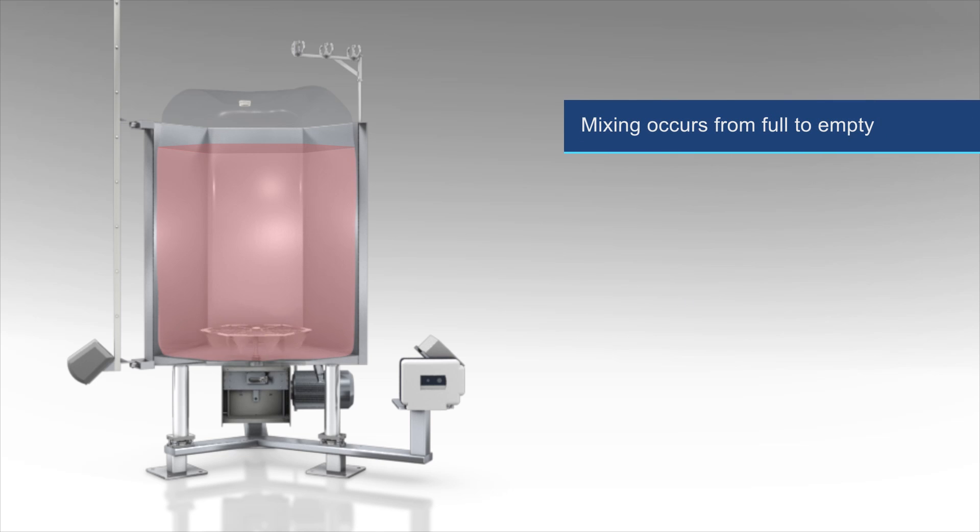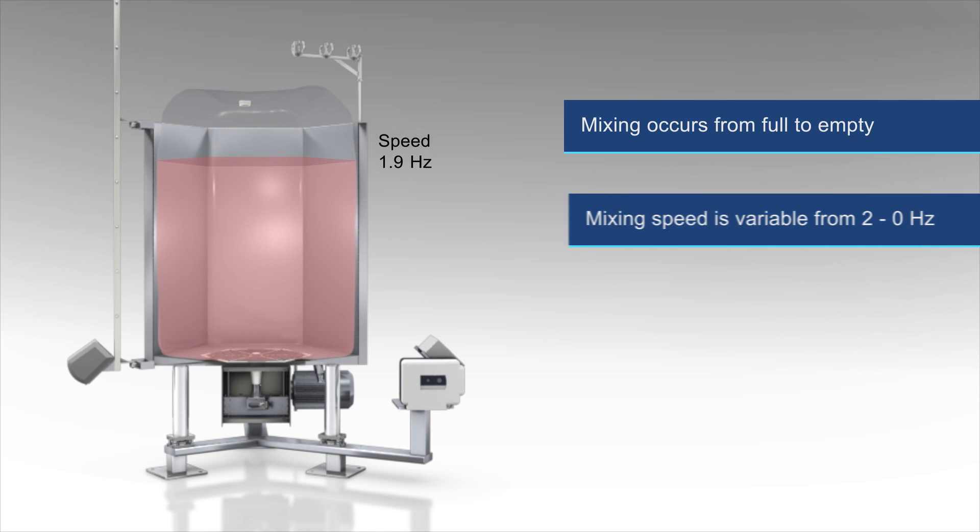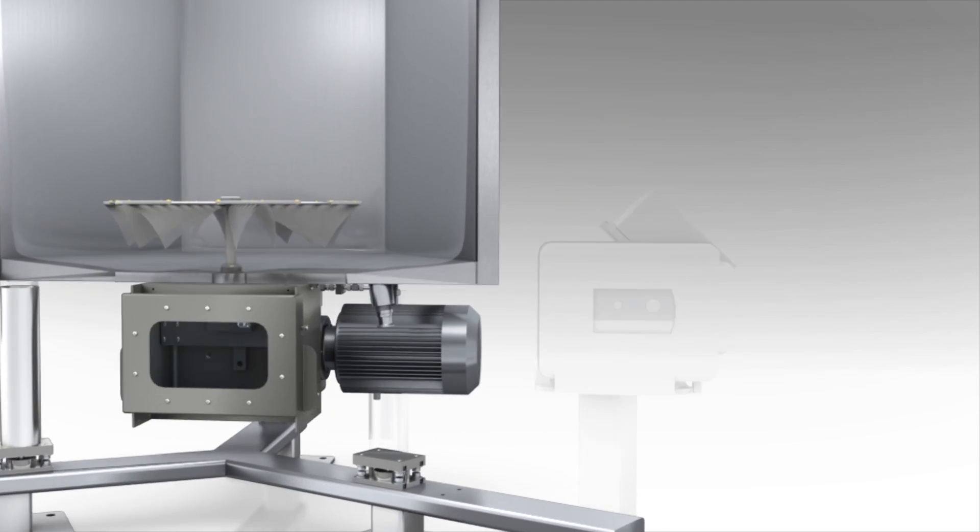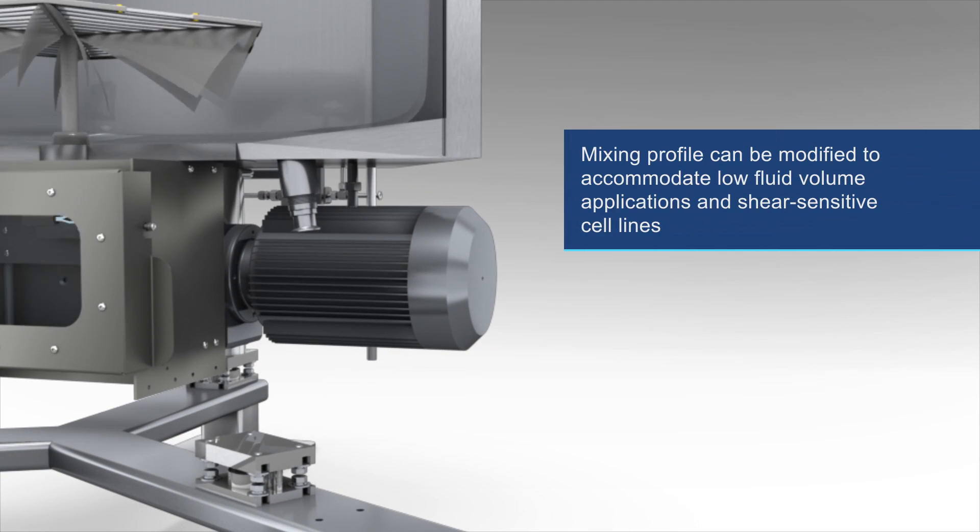Mixing occurs from full to empty. Mixing speed is variable from 2 to 0 cycles per second and is decreased as the liquid level approaches the top stroke of the mixer head at 20 to 30% of nominal volume. With the use of a servo motor and the agitation drivetrain, the mixing profile can be modified to accommodate low fluid volume applications and shear sensitive cell lines.